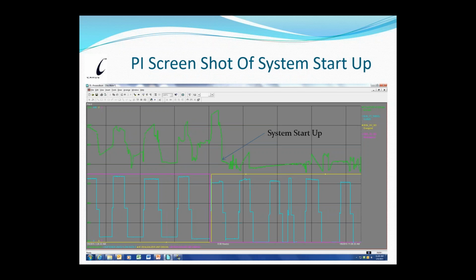This is a PI screenshot of the system startup. This is a trend screen that I can use for getting the PI data, pulling it from the system. The green one is our total city water flow. You can see that it goes up and down, and it's directly related to our water softeners running, as in the water flow through, or the operation of one of the RO train pumps. It comes on with a pre-flush, then a run, then a post-flush, and it's down again.